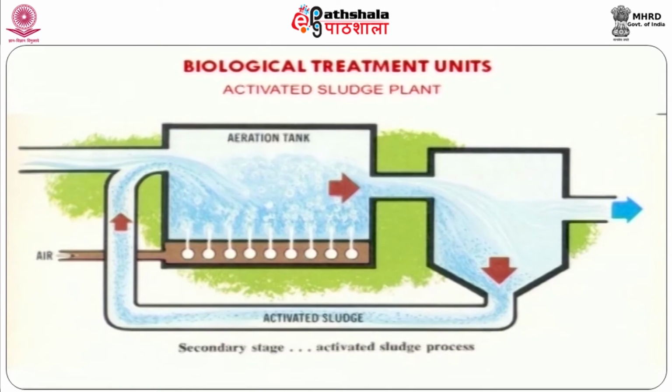The entire microbial culture will be in a suspended state, that's why the reactor is called a suspended growth culture, and the entire content will be collected in a secondary clarifier. With the help of gravity pull, we can segregate biological solids that will be generated during aerobic transformation. Roughly 30 to 40% of the biological solids are sent back to the aeration tank to keep the microbial population in the aeration tank at 2000 to 3000 milligram per liter.